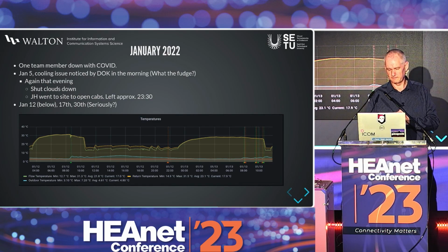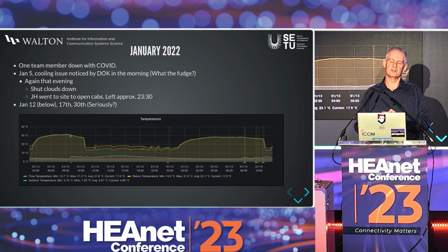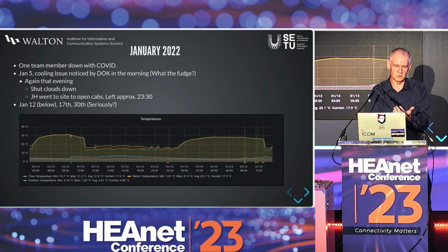Long story short, when it got too cold, the chillers were switching themselves off. A failed sensor meant free air cooling wasn't engaging, which was hilarious because it was below 4 degrees most of the time — and it was a failed sensor. It took a long time to get diagnosed, and because of the holiday season it was difficult to get an engineer on site — we're just one site among many with issues over Christmas — and it was hovering around 4 degrees or less every night.